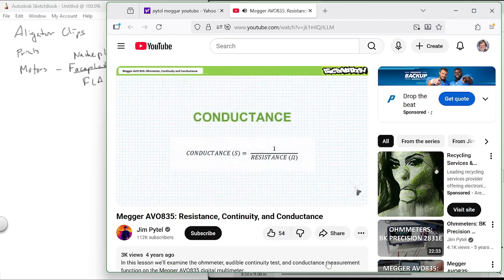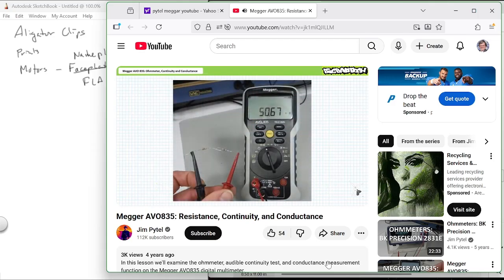The Megger AVO 835 additionally offers a conductance measurement in units of Siemens, where conductance is 1 over resistance, and 1 Siemen is 1 over 1 ohm. To place the AVO 835 into conductance measurement mode, rotate the selector switch to the ohm meter function and press the yellow mode button twice.